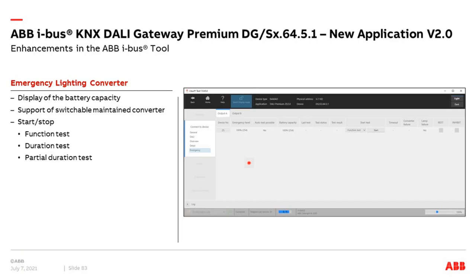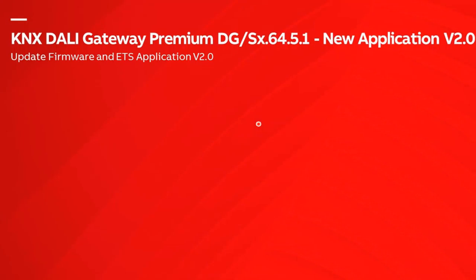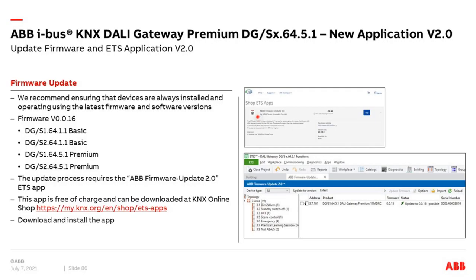On the emergency converter page there are also new features: we now support the switched maintained converter, and there is a column showing battery capacity. You can select and run a function test, duration test, or partial duration test, and see the test status (idle or running) and results (successful, failed, etc.).